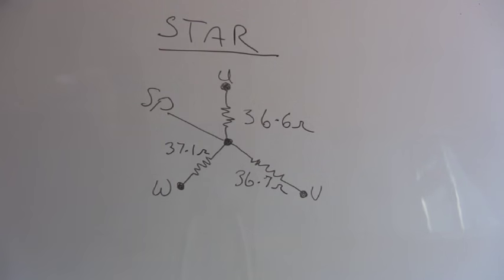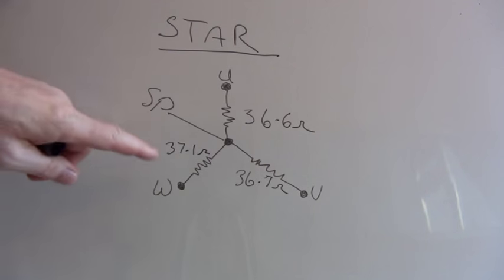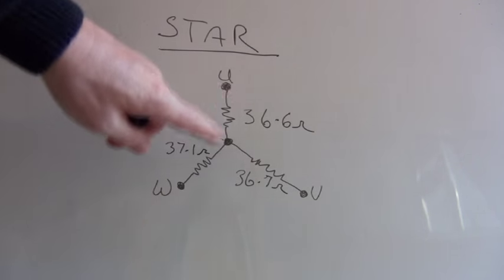Allowing a little bit of resistance for the terminations, that motor looks fairly balanced. They're approximately all the same reading, just allowing a little bit of resistance for the terminations. So I would say that that motor is balanced and it would function correctly.